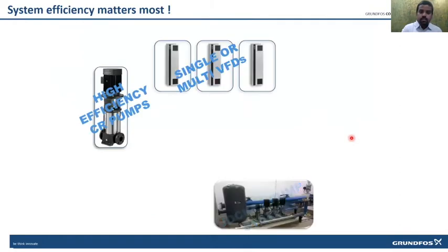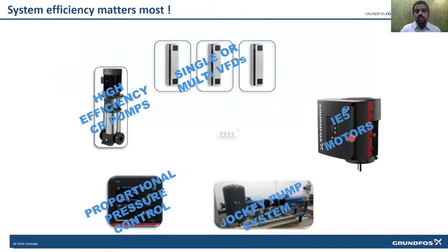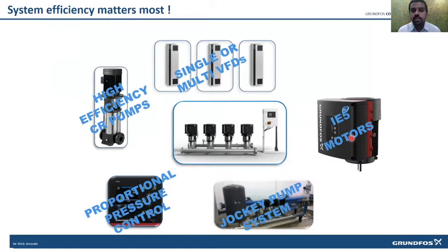So henceforth, we should not see a water distribution application only with respect to pump efficiency. We need to see it as system efficiency. Even today when we talk about buying hydro boosters, we say pump efficiency at 80%. We should not see it from that perspective. We should count what the motor efficiency is, what the VFD efficiency is, and how my system behaves at part load. So the simple terminology we are looking at henceforth for an efficient system is how much specific energy we are going to consume to move 1 liter of water. That defines the system efficiency.